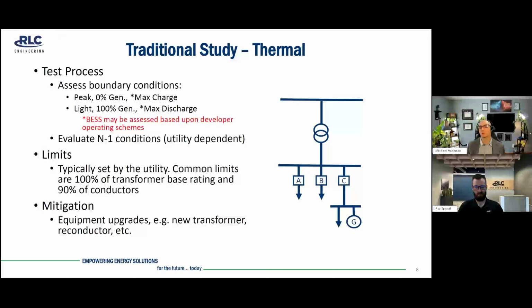Now, the caveat there is we do include and take into account what the developer wants as far as an operating scheme for the battery. However, if that's not specified, we'll typically look at worst case conditions. Another thing to keep in mind when looking at thermal evaluations is some utilities will include N-1 conditions, which is essentially loss of an element in the system. Usually for a system impact study, that is looking at loss of a specific load pocket because that load is going to offset a portion of the generation. And if you lose that load pocket, you're going to see a greater export condition. So you're going to see higher thermal loading on some of your equipment.